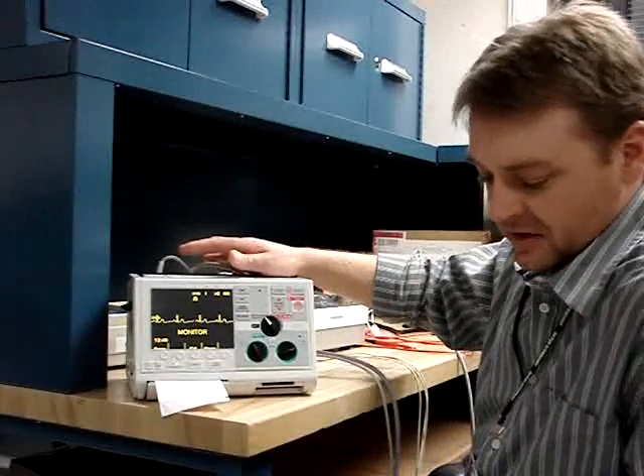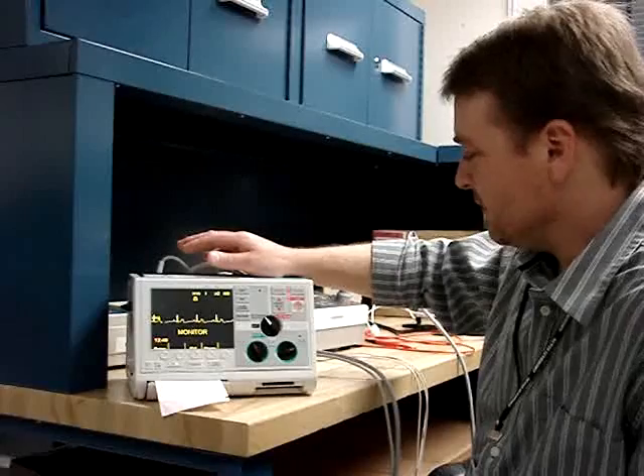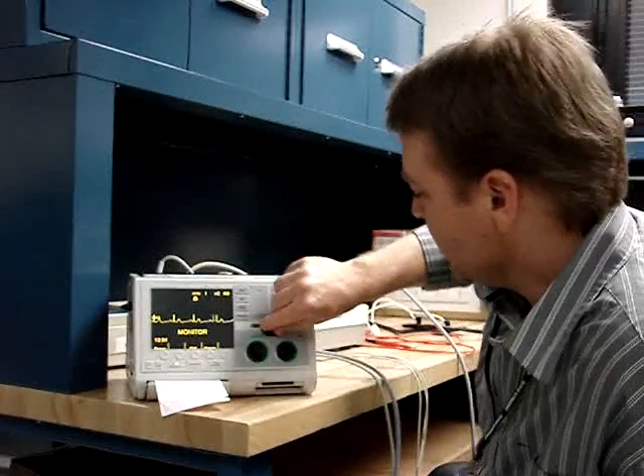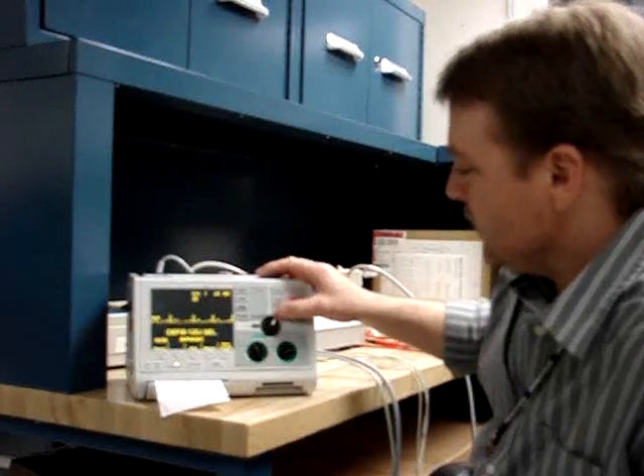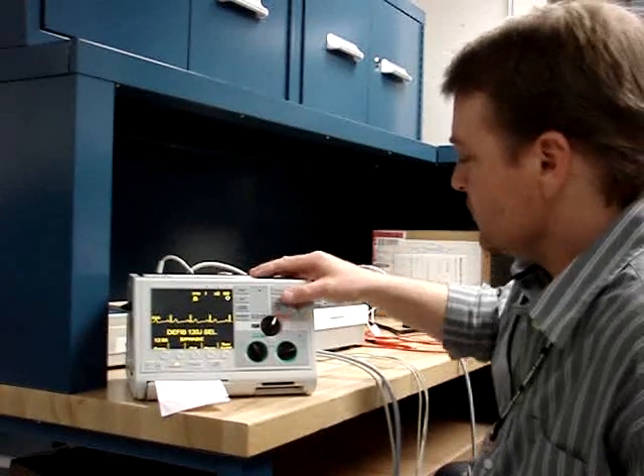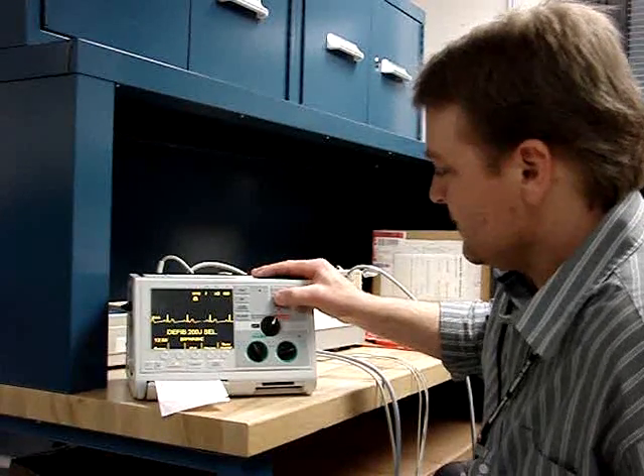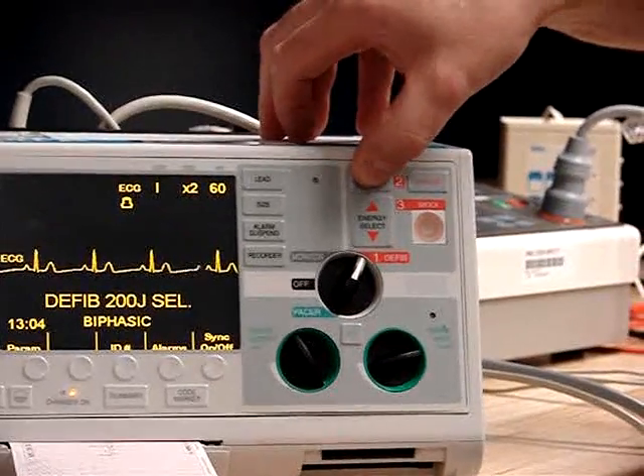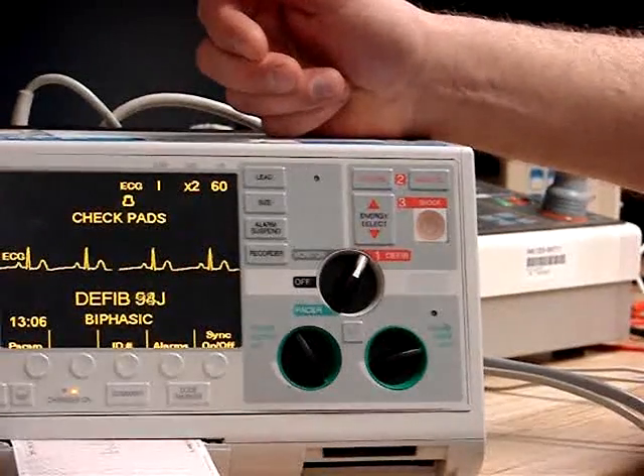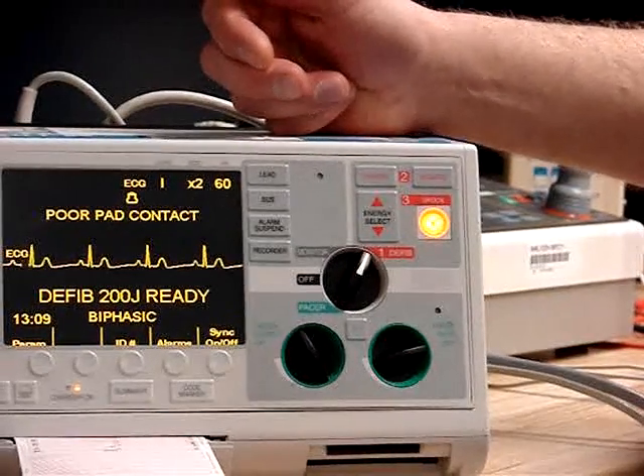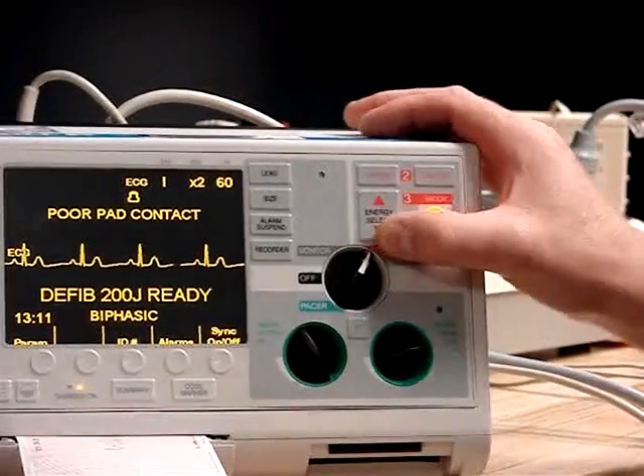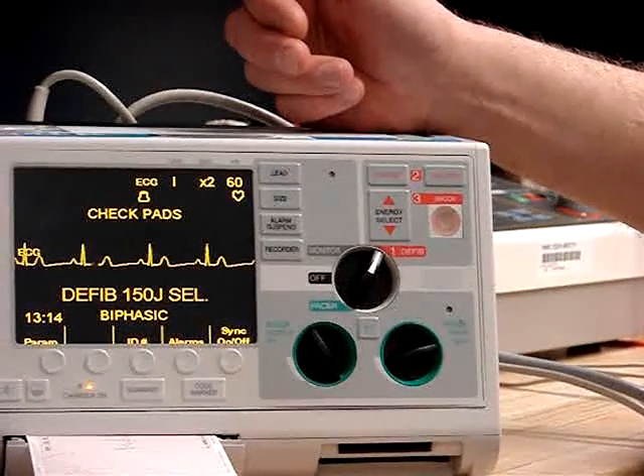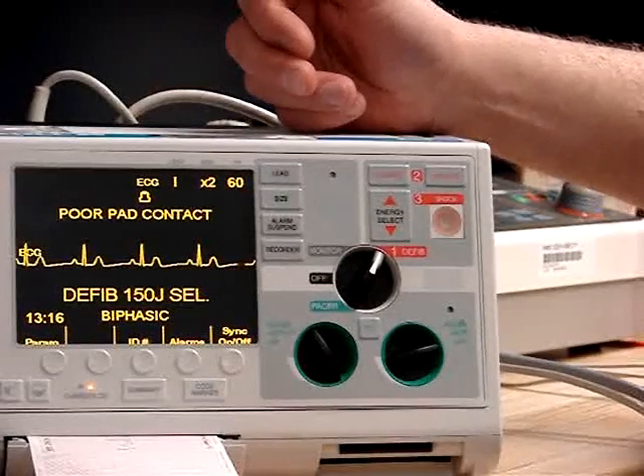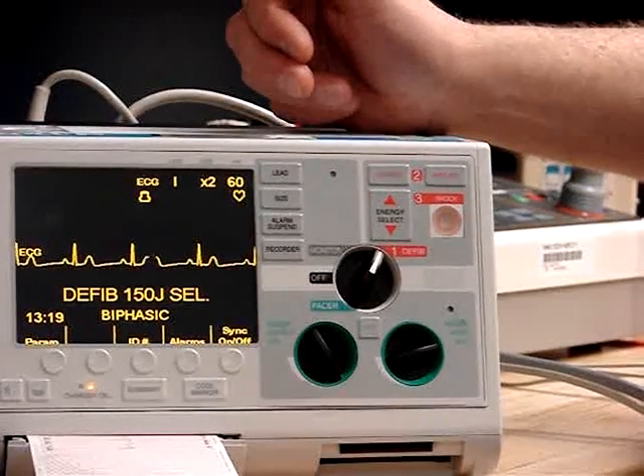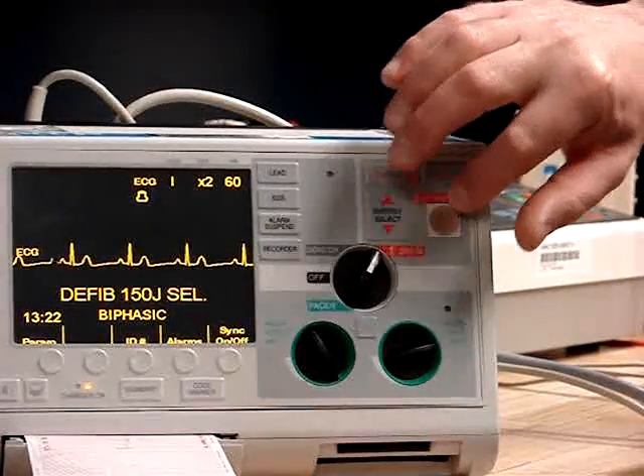Now we'll be checking the internal discharge of the Zoll defibrillator, and to do this, first we select defib, and we want to set the joules to the max energy setting, and then we want to charge it. We'll know it's going to be charged by the shock light will be illuminated. Now we have full shock. We should be able to push any button and the unit will internally just discharge all of its energy safely without damaging the machine, and we know it's discharged by the shock light going off.